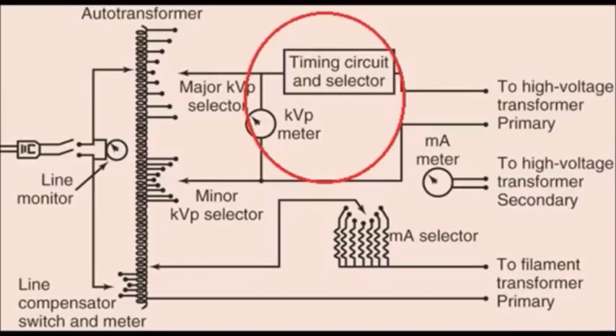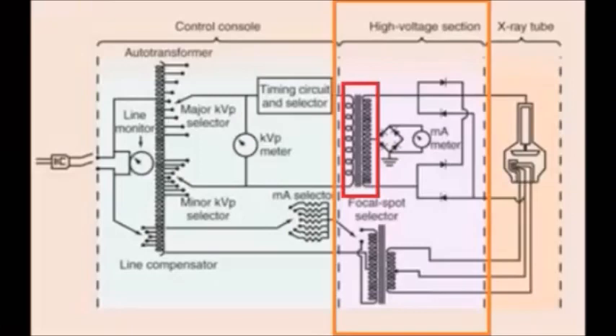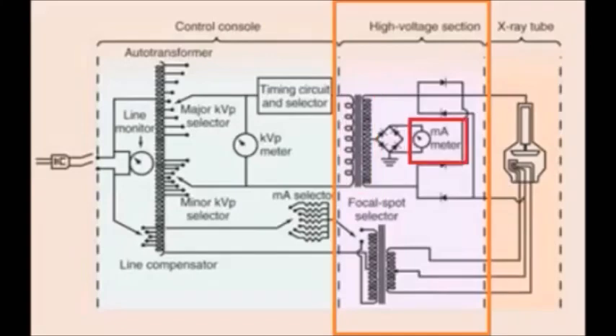At the high-voltage step-up transformer, voltage is increased by a factor of about 500 to kilovolts and amperage is reduced. Unlike the auto transformer, the step-up transformer operates on mutual induction. On the secondary side of the step-up transformer is the amp meter, which reads current after the exposure.